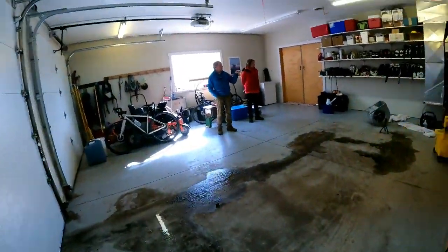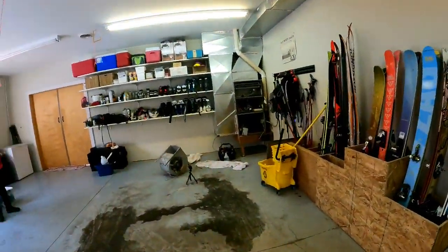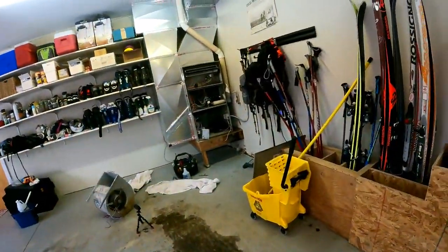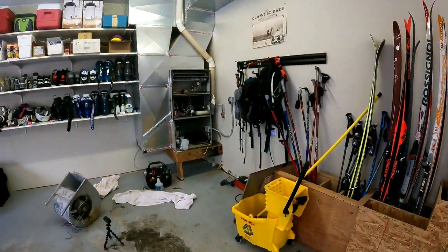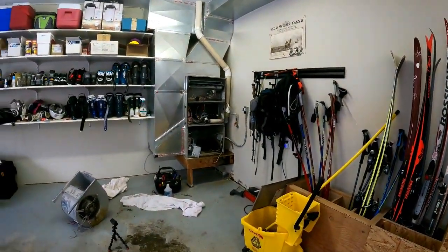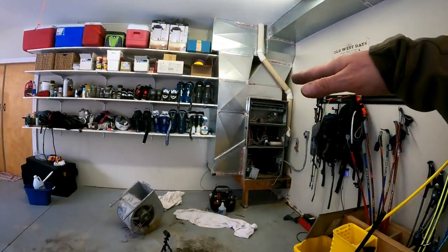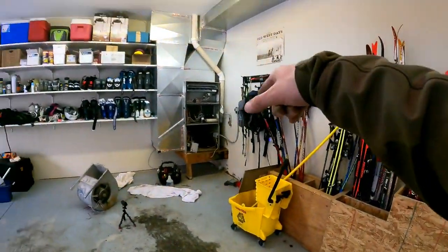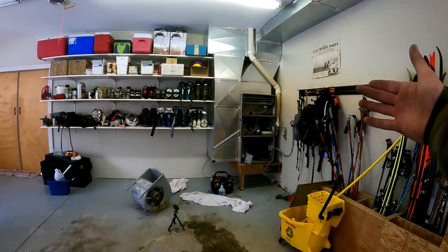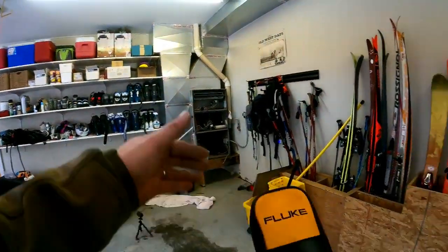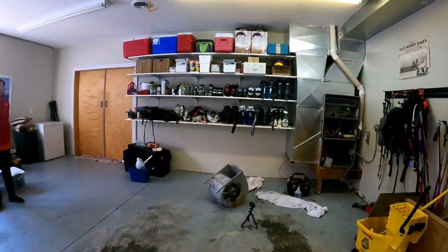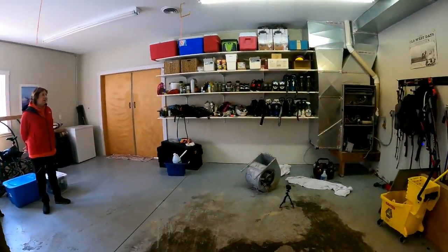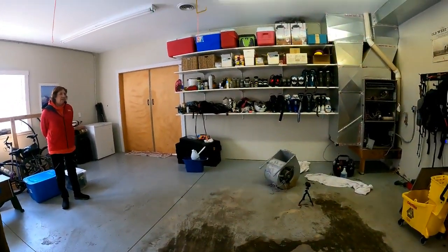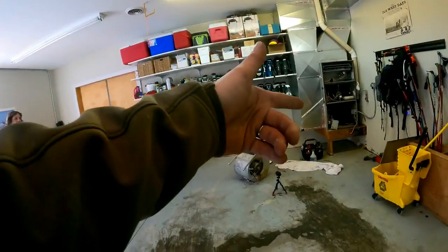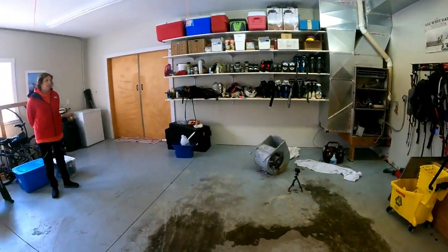Condensation water comes down into the pump from here, and when the water gets up in the pump to a certain height, the pump turns on. There's a float that comes up and turns the pump on. But with no power to the pump, the float came up and it didn't come on, so the water just came out of the pump. Everything makes perfect sense now, that's why I can't find water anywhere, because it's residual water from that pump overflowing.